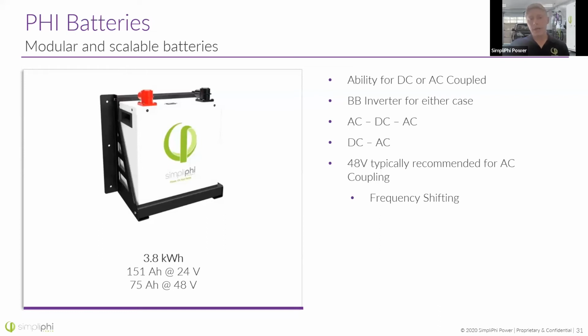Now, you're probably wondering, can this battery do AC or DC coupling? It can do both. So I'll say this again, a battery is a battery. It handles DC power only. So regardless of whether you're AC or DC coupling, you will need a battery-based inverter to handle the charge currents and loads. The battery-based inverter is kind of the buffer and the maintainer of the battery bank. With that, our batteries can be AC or DC coupled. Either way is not a problem. However, keep in mind 48 volts is recommended for AC coupling. A lot of the equipment that has frequency shifting and does AC coupling only operates at 48 volts anyway.